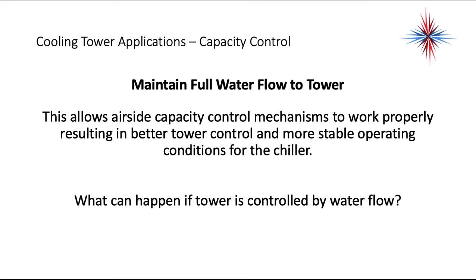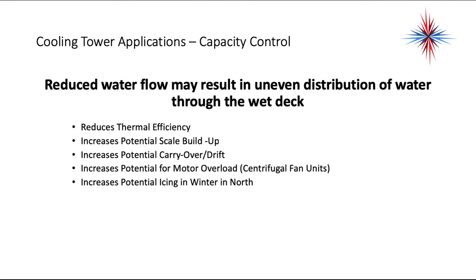What can happen if the tower is controlled by water flow? Reduced water flow may result in uneven distribution of water throughout the wet deck. The spray heads or dam at the top could not have enough water to produce even flow. This reduces thermal efficiency, increases scale buildup, increases the potential for carryover and drift — that's the loss of water from the tower — increases potential for motor overload, and increases potential icing in the winter in the north.